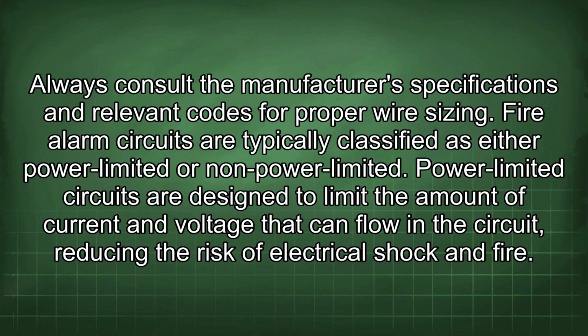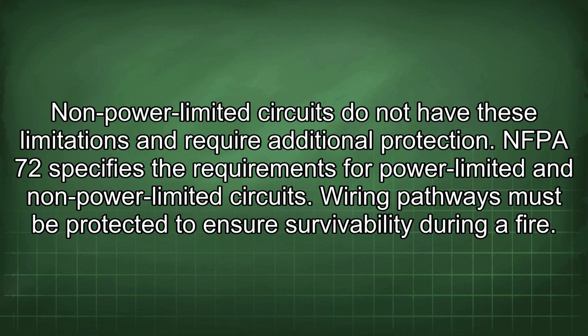Fire alarm circuits are typically classified as either power limited or non-power limited. Power limited circuits are designed to limit the amount of current and voltage that can flow in the circuit, reducing the risk of electrical shock and fire. Non-power limited circuits do not have these limitations and require additional protection. NFPA 72 specifies the requirements for power limited and non-power limited circuits.